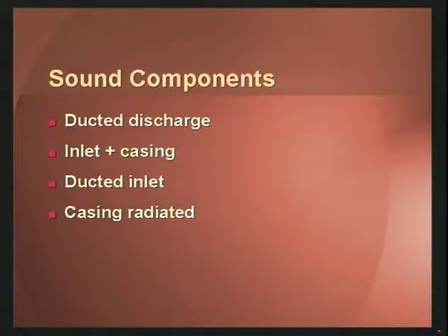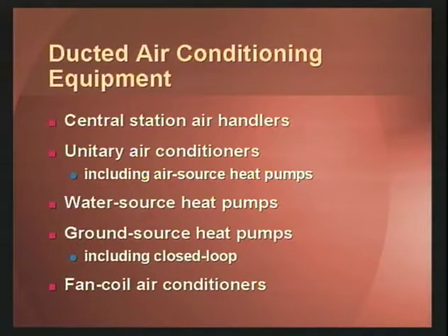This is for catalog products, ducted air conditioners, and air handling units. The sound components that we get from ARI 260P are the ducted discharge, the inlet plus casing component, the ducted inlet, and casing radiated. And in some cases, when needed, free inlet and free discharge. Products covered under ARI 260P are air conditioning equipment, such as central station air handlers, unitary air conditioners, including air source heat pumps, water source heat pumps, ground source heat pumps, including closed loop ground source heat pumps, and fan coil air conditioners that are ducted. ARI 260P is in the final draft stages and is ready for the process of being approved in the spring of this year.